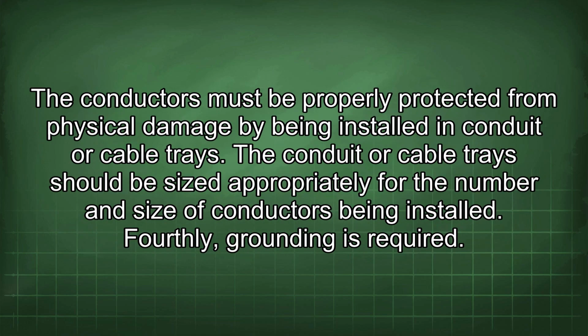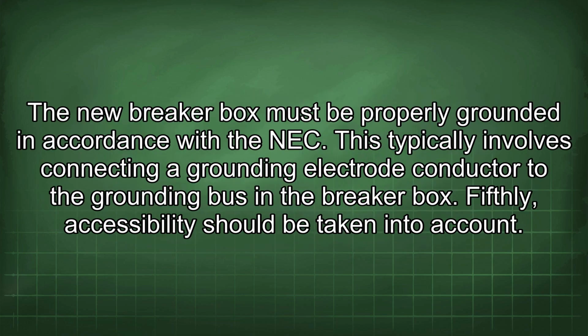The conductors must be properly protected from physical damage by being installed in conduit or cable trays. The conduit or cable tray should be sized appropriately for the number and size of conductors being installed. Fourthly, grounding is required. The new breaker box must be properly grounded in accordance with the NEC. This typically involves connecting a grounding electrode conductor to the grounding bus in the breaker box.